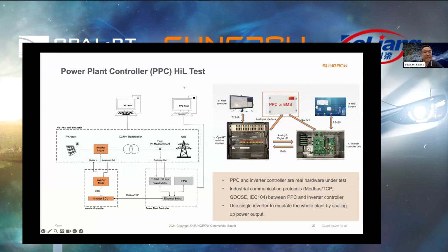Okay, another case is the power plant controller HIL test. So in this case, based on the last inverter-only test case, we here included another PPC or EMS. So it connects via IEC 104 or GOOSE communication protocols directly to our inverter controller.